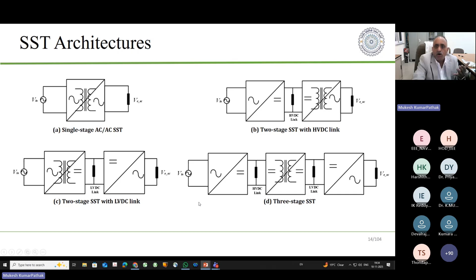So the first one is a single stage with direct AC to AC conversion. It has high efficiency and high power density, but it has limited functions. And the two-stage options, B and C, have one DC link either on the HV or LV side. When you have a DC link, you are essentially using electrolytic capacitors, and that will make it bulky. But at the same time, integration of renewable energy sources is possible. The third possibility, if you look back, has an active rectifier on the input side, then an isolated DC-DC converter and an inverter. So there are more functionalities here, and bulky energy storage elements are required, but you have both high voltage and low voltage DC links.